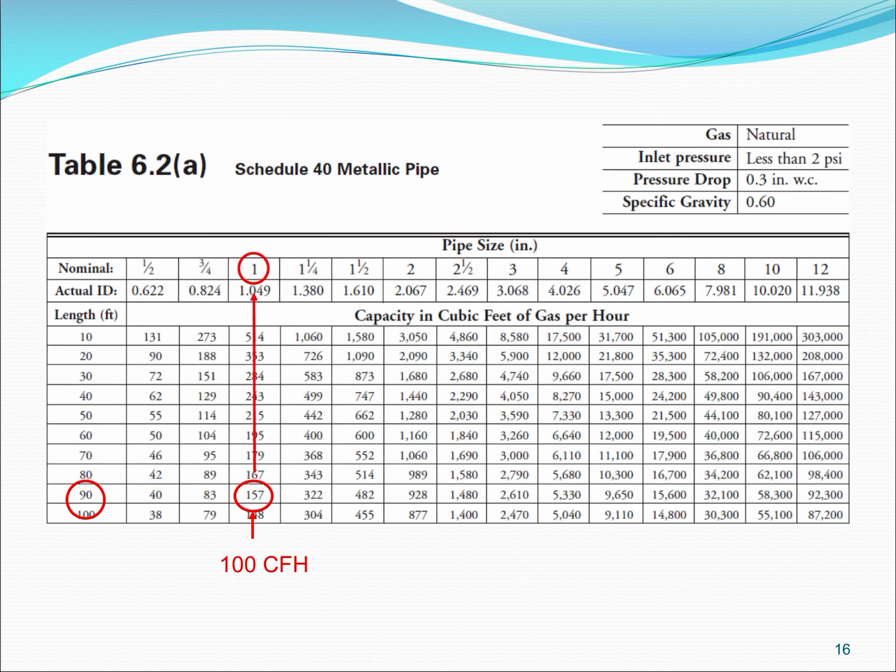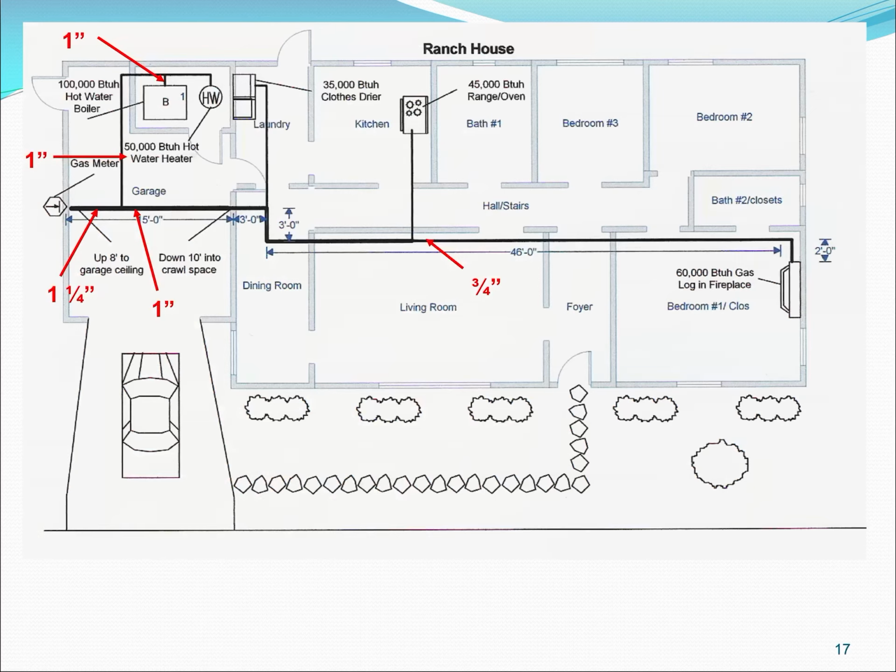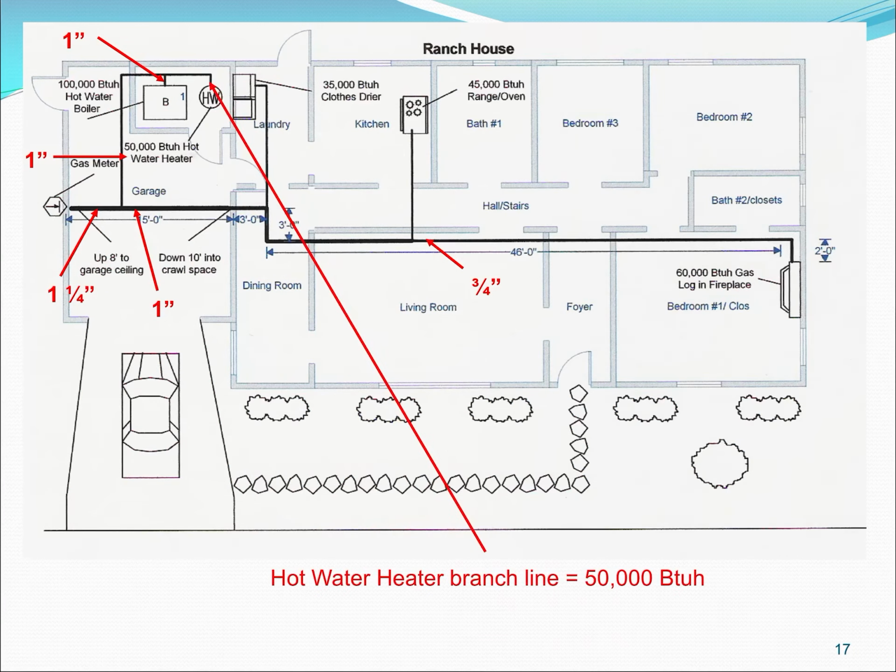So in this case, the boiler is going to need a 1-inch line going directly to that. As I had mentioned in other YouTube videos, you're going to have to reduce it accordingly when you get near that boiler, because that boiler most likely is only going to have a 1/2 or a 3/4 inch inlet. You just bring it as far as you can, and it should be good.